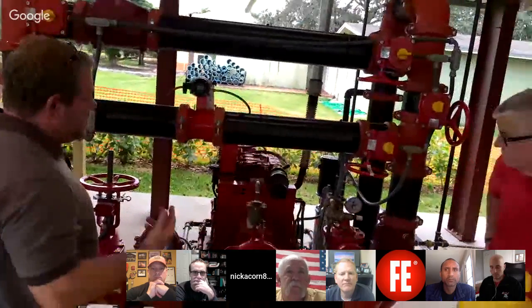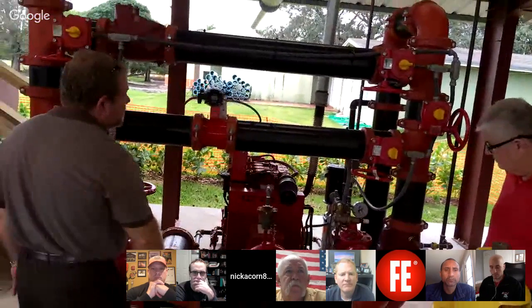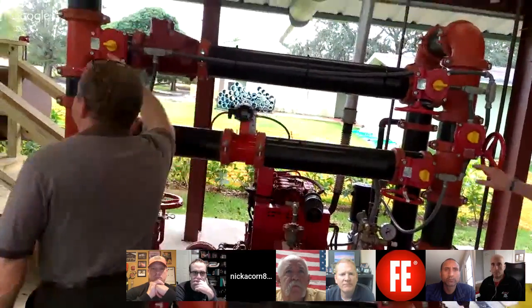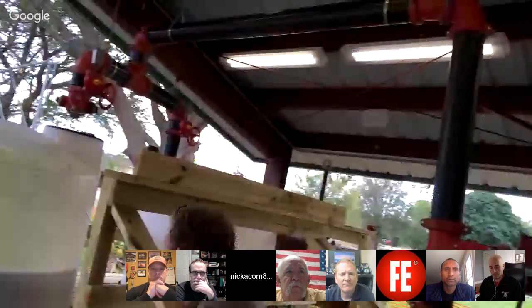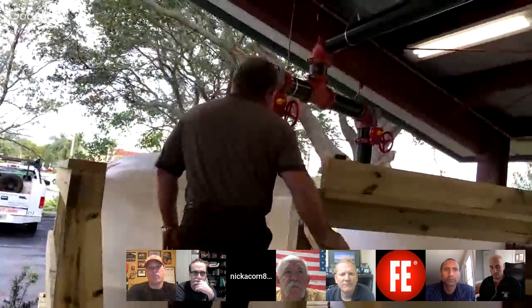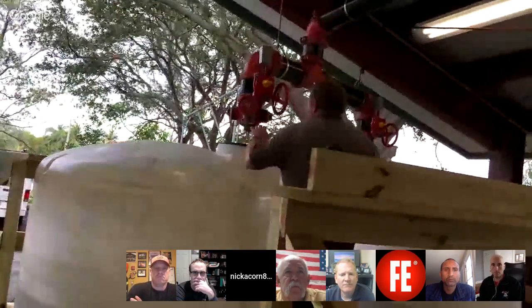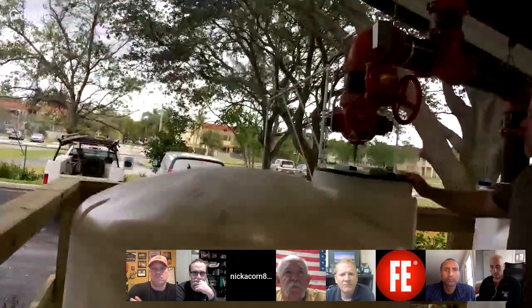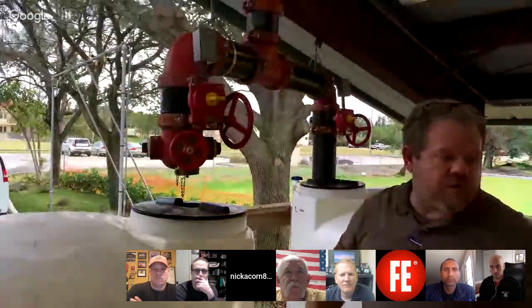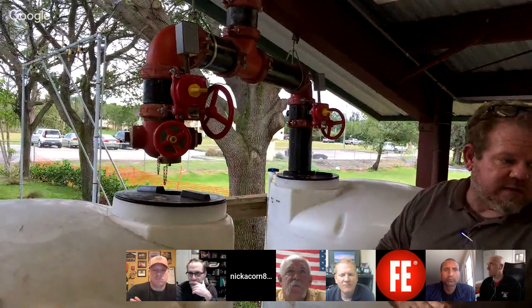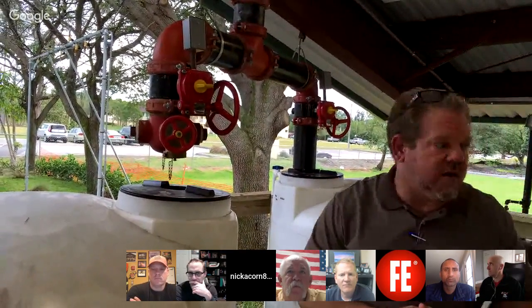That's brand new. And the second way that we're able to test the fire pump is essentially through the tests that are back up to the holding tanks. Basically open up the reservoir and put our flow meters directly on with the nozzles. We're flowing the water back into the tank. We were doing some of that this week, and we were doing some fire pump testing.